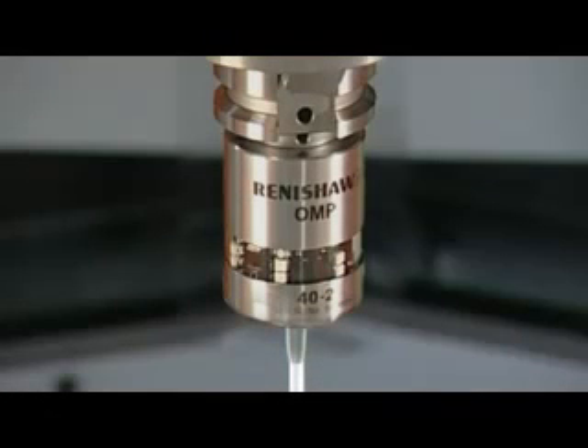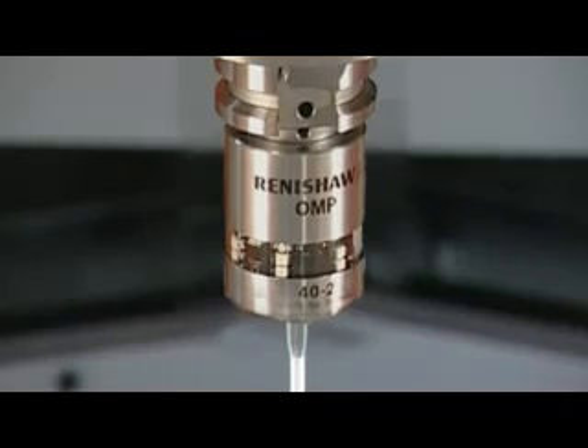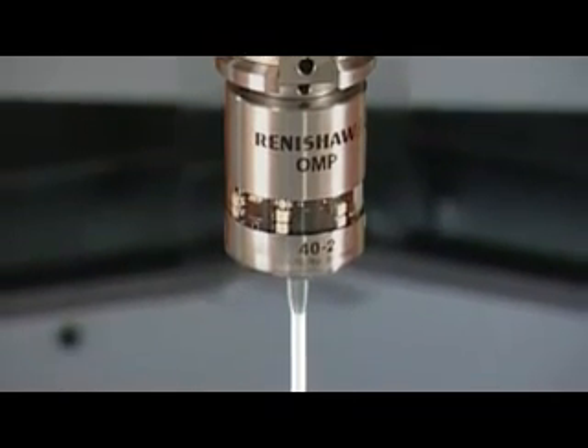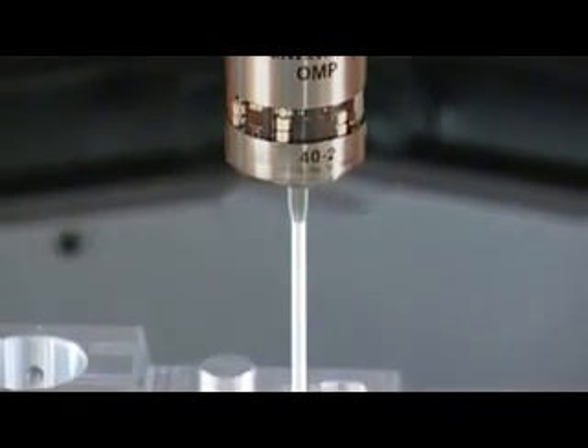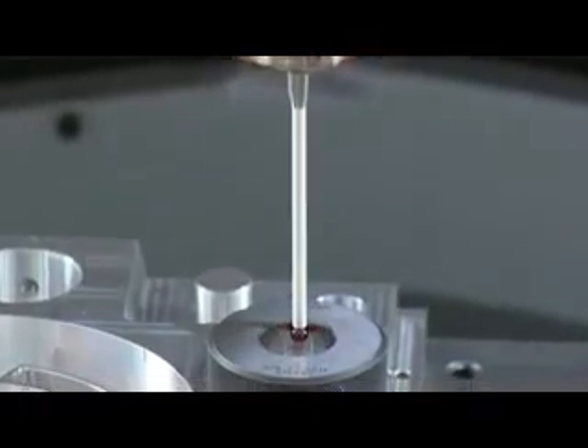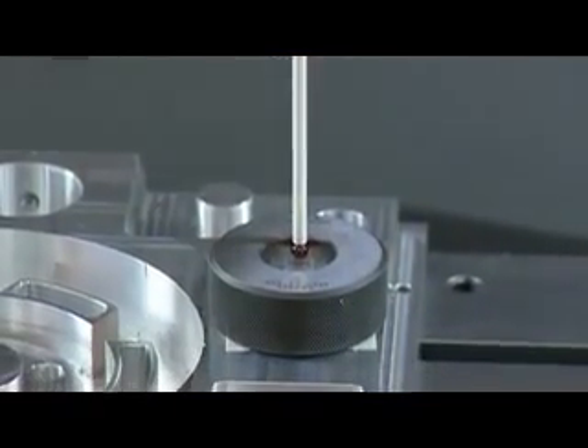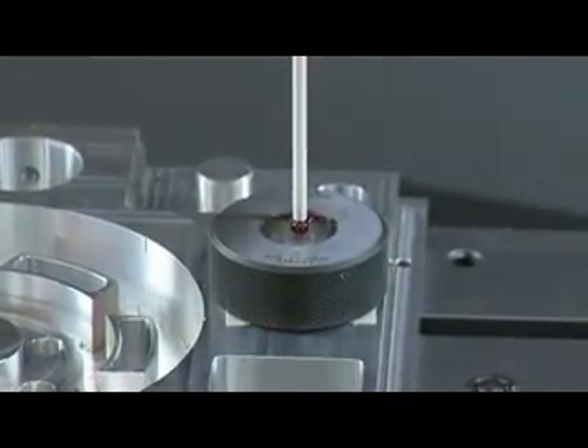Spindle probe calibration is required to minimize the amount of mechanical, electrical and environmental errors which would otherwise be included in the measurement data. Once the initial setup has been completed, the automatic calibration cycle can be run at intervals that suit the machining process requirements.